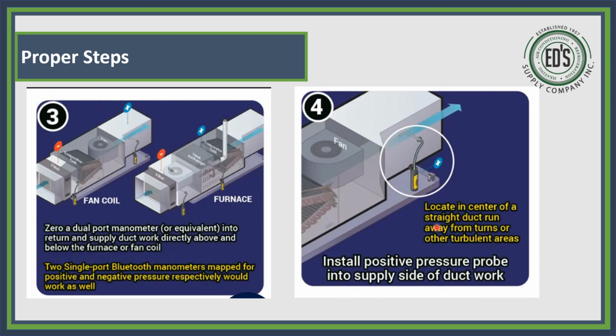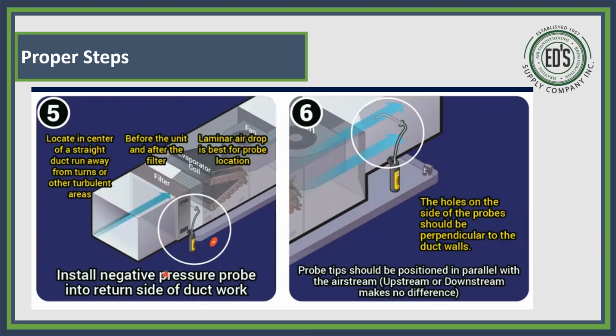Okay, locate in the center of a straight duct run away from turns or other turbulent areas. Like I said, you're going to have turbulence down in here. You want to go right dead in the center because that's where that airflow is going to be. Then locate before the unit and after the filter. It would do no good if I checked it here because the filter is a resistance. I want to test the airflow here, what that motor's doing, on the back side of that filter, not on this side, on the back side.